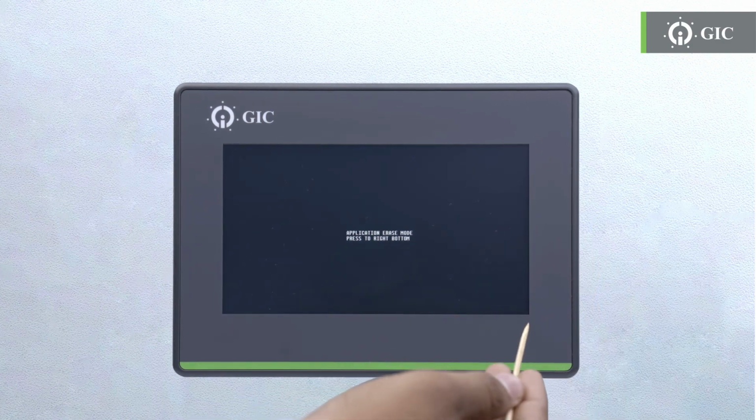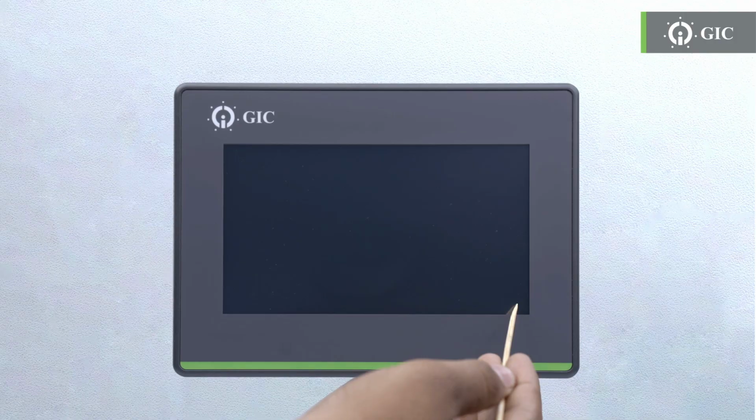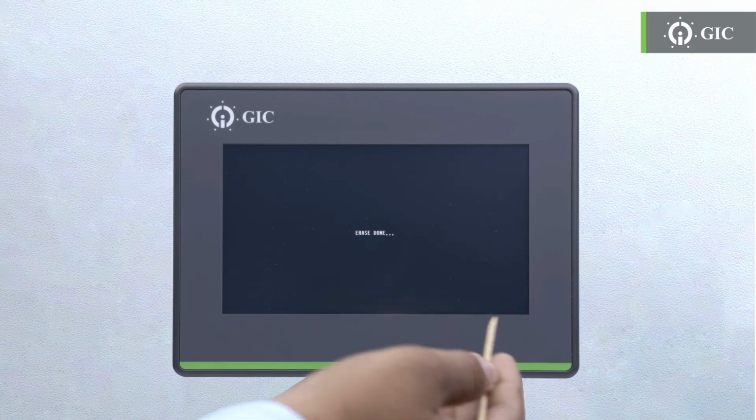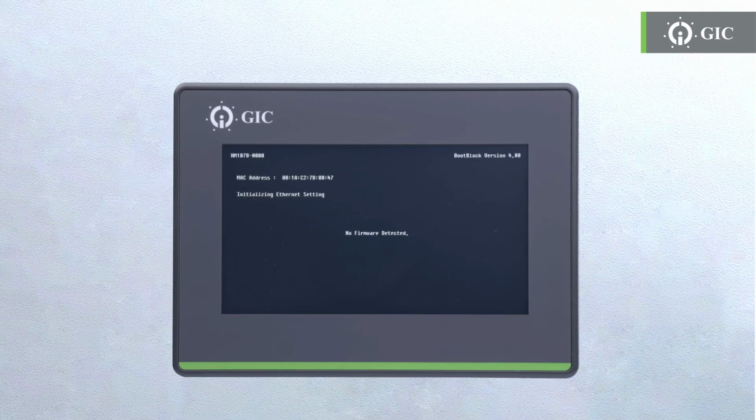Step 3. Press on the right side bottom corner, holding it for 3 seconds. This confirms your action of application erase. The action is completed as the message, "Erase done," illuminates the screen. The device will now reboot. Firmware erase and application erase are not required regularly. You may perform these only when a problem may arise.